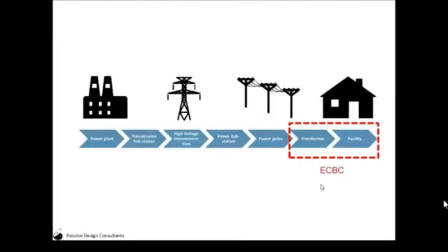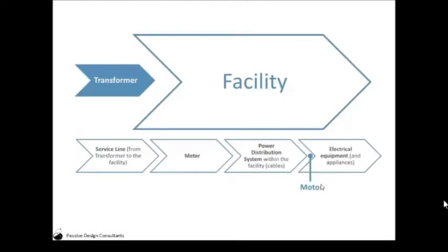Further, on the electrical side, the electrical requirements are only mandatory in nature. In ECBC, there are no prescriptive requirements. The mandatory requirements basically deal with the scope of the electrical system, which starts from the transformer and the electrical systems within the project or within the facility. Beyond the transformer, the distribution network of the central grid, etc., are not part of ECBC compliance for a project, as they are not in the purview of the project team. Hence, the transformer and the electrical services which come under the facility or the project need to meet the ECBC requirements.